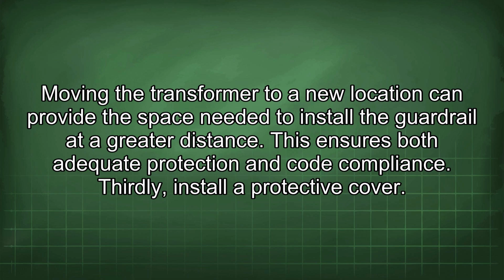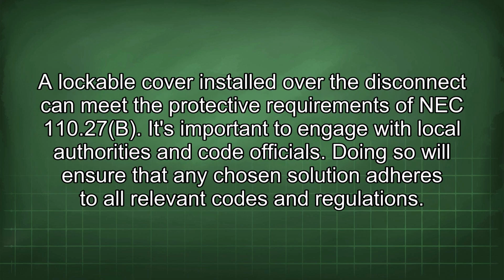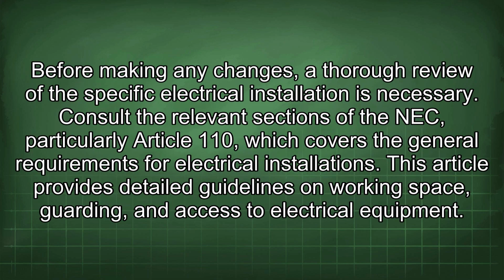Thirdly, install a protective cover. A lockable cover installed over the disconnect can meet the protective requirements of NEC 110.27(B). It's important to engage with local authorities and code officials. Doing so will ensure that any chosen solution adheres to all relevant codes and regulations. Before making any changes, a thorough review of the specific electrical installation is necessary. Consult the relevant sections of the NEC, particularly Article 110, which covers the general requirements for electrical installations. This article provides detailed guidelines on working space, guarding, and access to electrical equipment.